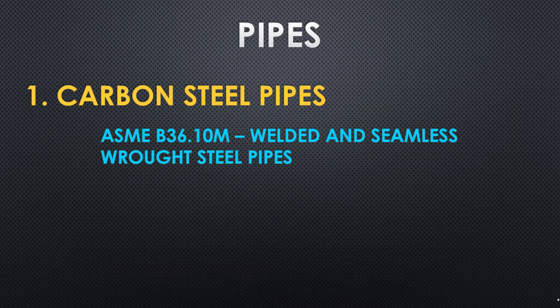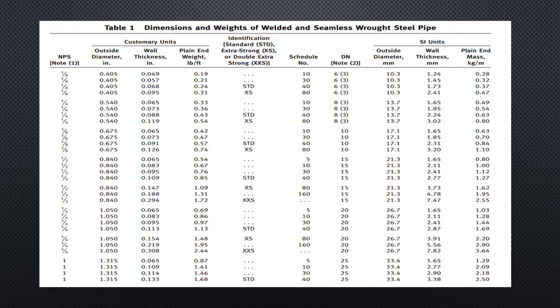In pipes, the first type is the carbon steel pipe. The dimensional details of carbon steel pipes you will get from ASME B36.10M, and the description says 'welded and seamless wrought steel pipe.' This is the cover page of the standard. In the standard, you go to Table 1, where you have two unit systems: one is the imperial unit system based on inches, and the other is the metric unit system based on mm.